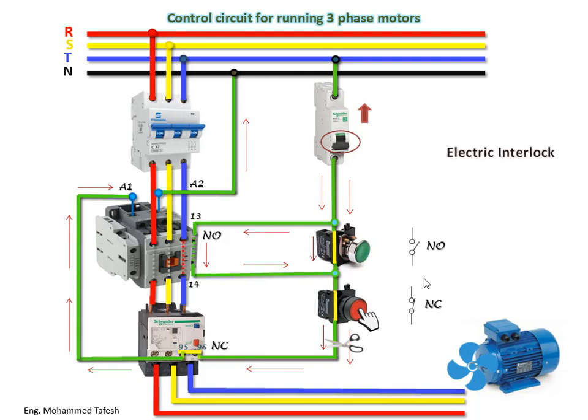An important point: if the electric current exceeds the limit set in the overload — for example, if the full load motor is 16 amperes and the current rises to 18 amperes — the overload device will sense this value and separate contact points 95 and 96 from each other, making them open. In this way, the circuit is disconnected, protecting the motor from overheating caused by excessive current.